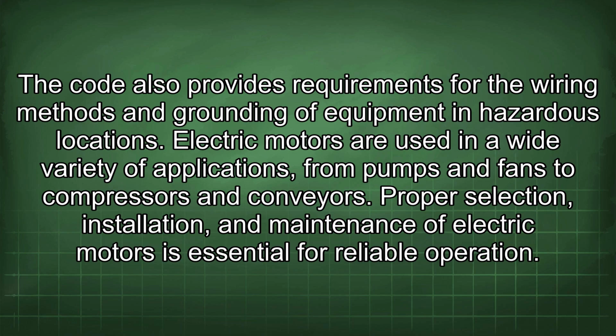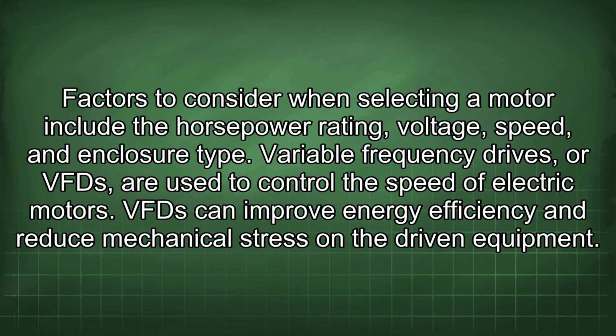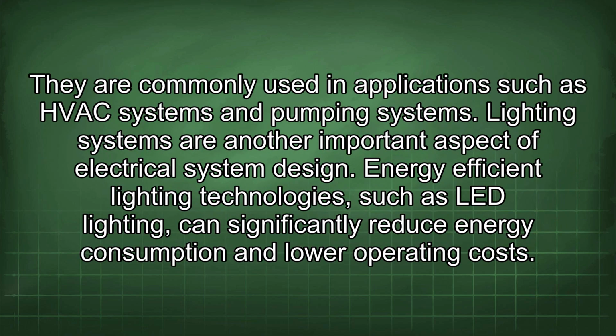Electric motors are used in a wide variety of applications, from pumps and fans to compressors and conveyors. Proper selection, installation, and maintenance of electric motors is essential for reliable operation. Factors to consider when selecting a motor include the horsepower rating, voltage, speed, and enclosure type. Variable frequency drives, or VFDs, are used to control the speed of electric motors. VFDs can improve energy efficiency and reduce mechanical stress on the driven equipment. They are commonly used in applications such as HVAC systems and pumping systems.